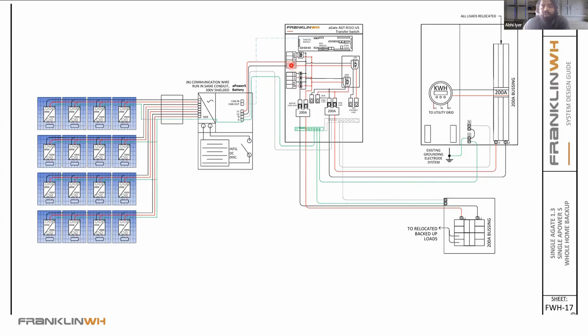If you have multiple aPower S units, depending on the number you have, you can land them on the backup lugs of the A gate. This ESS breaker on the A gate is rated for 125 amps, so it can support up to 2 batteries. But if you need more than 2 batteries, you'll need to aggregate them to a generation panel or battery combiner panel.